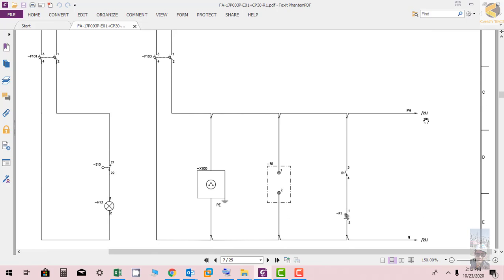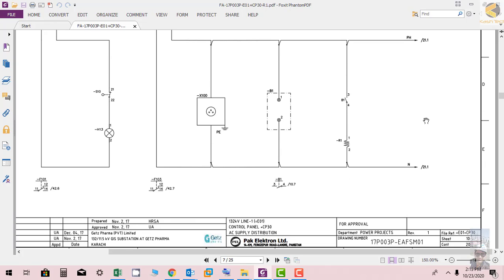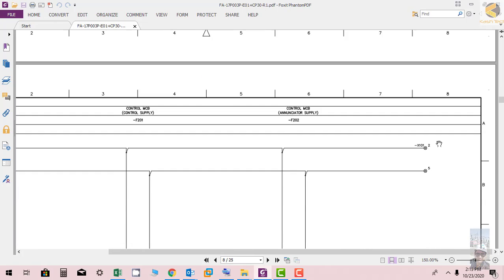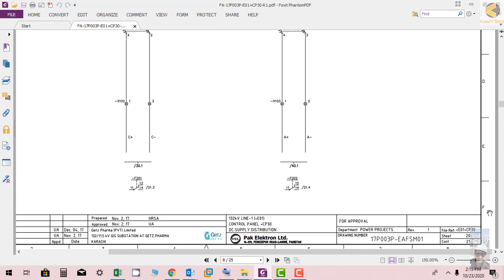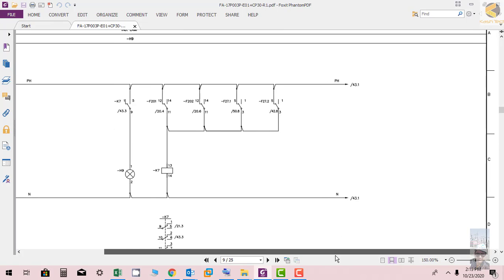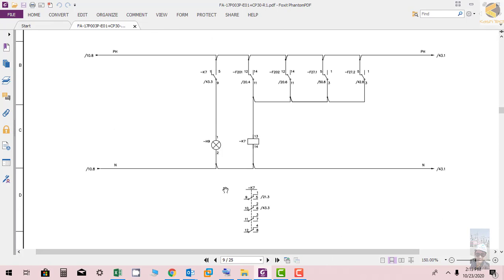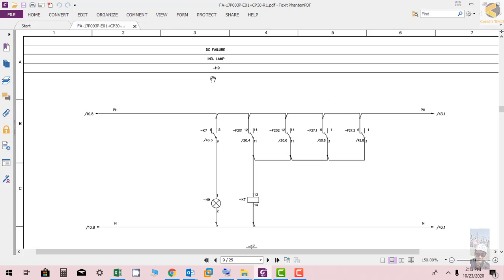Now further the loop AC loop is going to sheet 21.1, so let's see what is it doing. We'll go to sheet 21. You can see the AC loop is coming also here. If you can see DC failure indication, if this is fail the indication H9 will be energized through AC supply and K7 will close and then H9 will be lit, which is showing that the DC supply of the panel is fail.